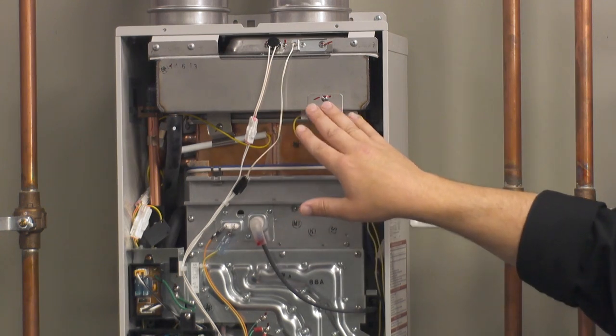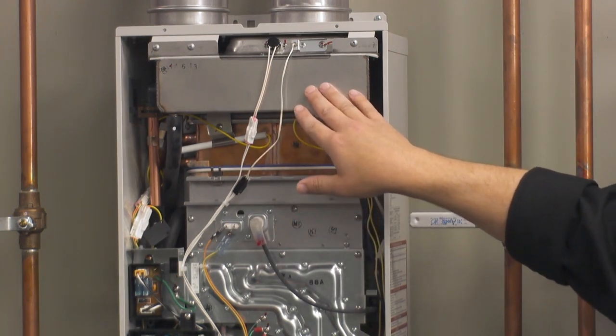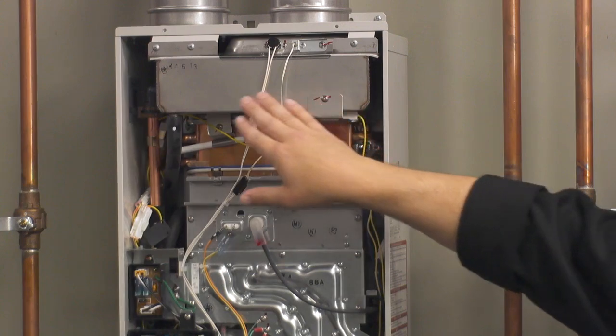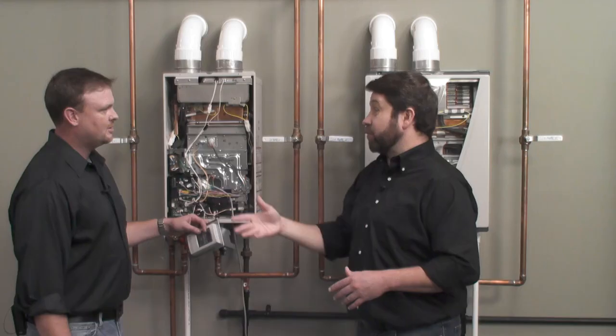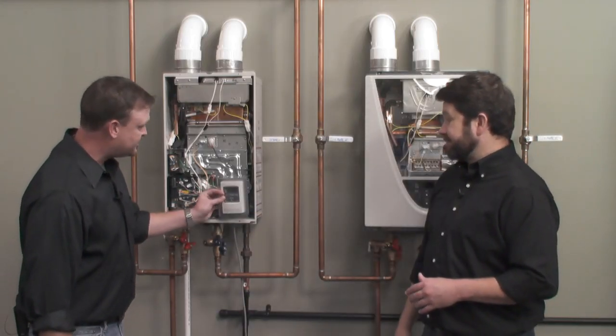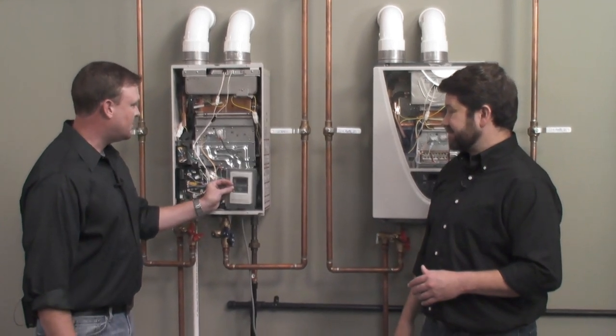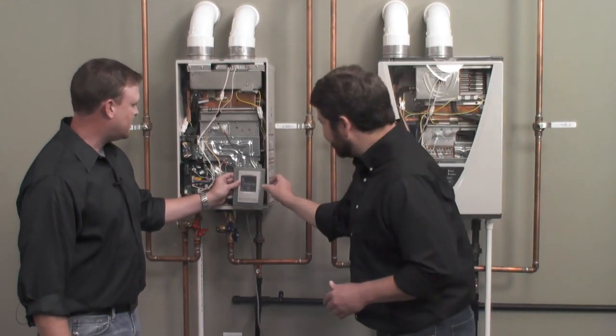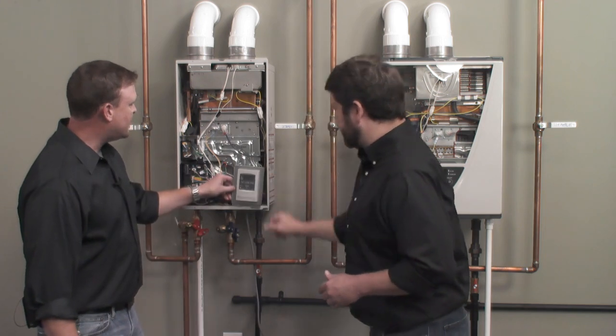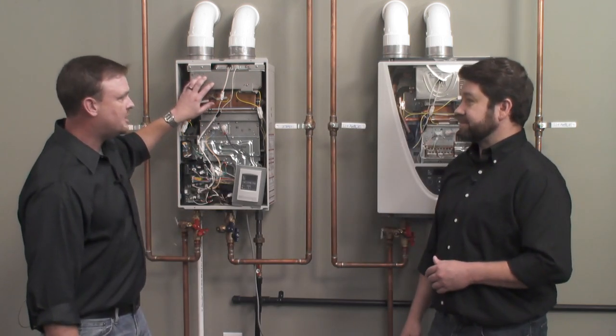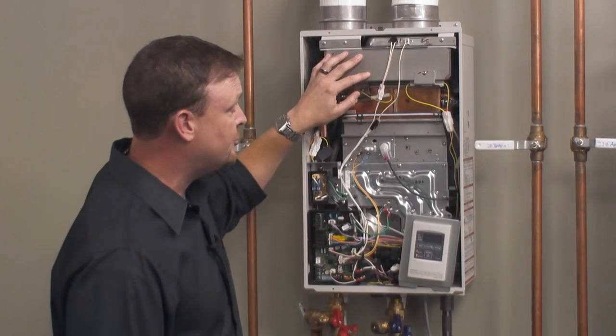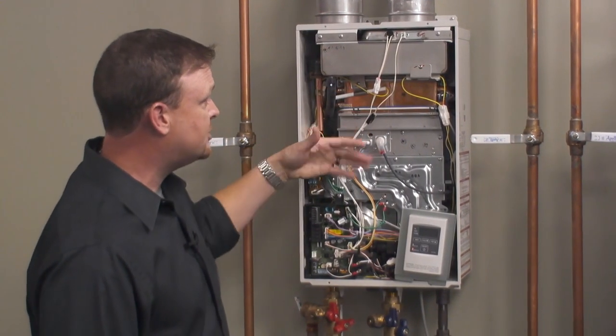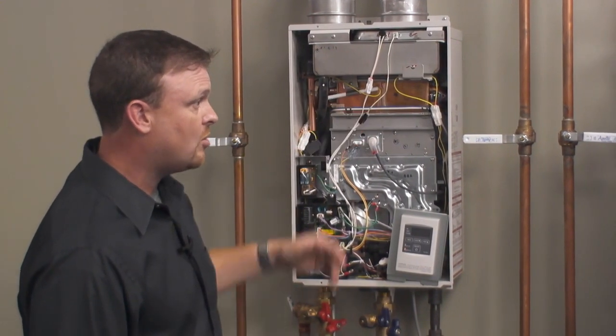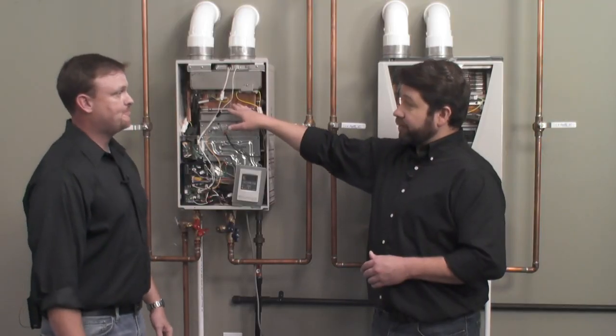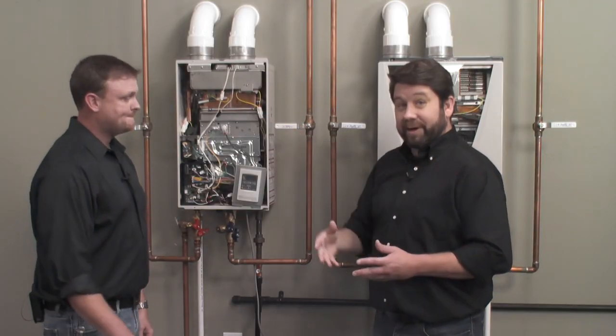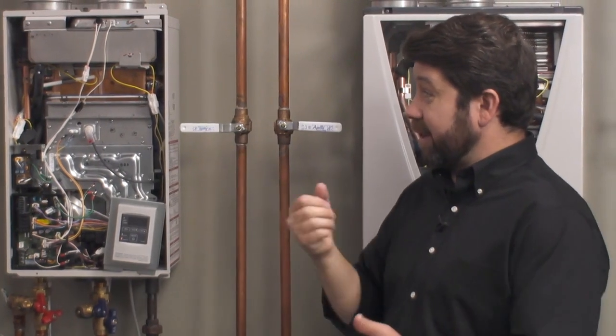So to get a little bit more heat out of those flue gases, we take those cooler flue gases with the coldest incoming water, and that gets us about 12% more efficient. So that's going to add to the efficiency of that water heater. All right, so you've got 12% being scrubbed off in the secondary heat exchanger. Our water's passing through there first, then going to our primary, and after it's running for a little bit, this will preheat that water coming through the primary, so that we've got warmer water hitting that copper heat exchanger and don't have to worry about condensing with super cold water hitting that copper right away.